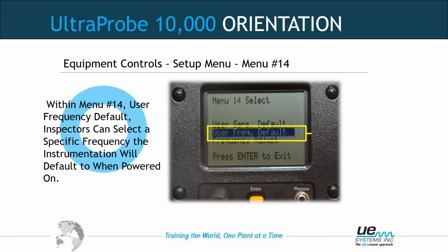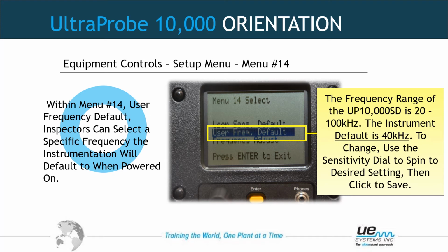The same for frequency default. Where does the unit come on? At UE Systems, we default the unit to 40 kilohertz and put the scanning module in it. So as soon as you get it and open the case, you could literally go find air leaks without touching it, other than pulling the trigger. Again, it does not lock you out of adjusting the frequency.